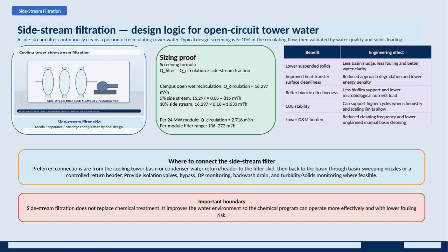With better control of cycles of concentration, filtration supports higher cycles when chemistry and scaling limits allow, leading to a more stable operation. Maintenance and operational burdens are also reduced, thanks to less frequent cleaning requirements and fewer unplanned manual basin cleanings. Regarding installation, the preferred connection points for the side stream filter are from the cooling tower basin or the condenser water return or header.